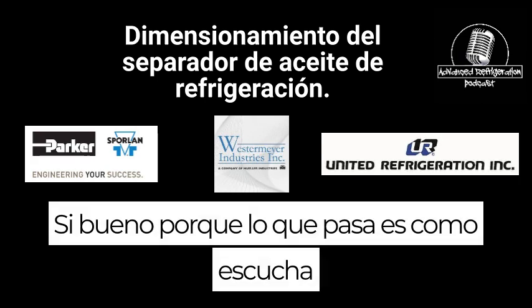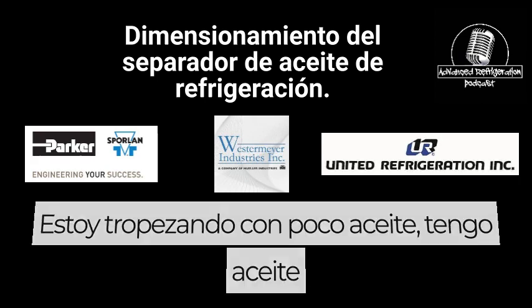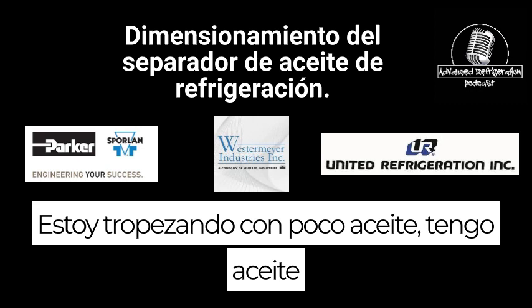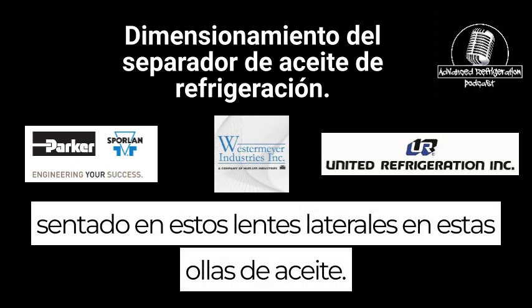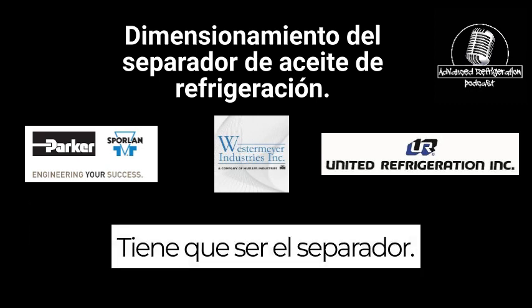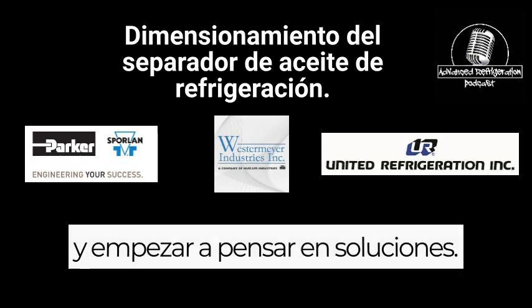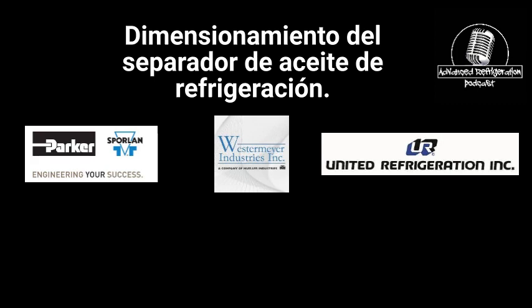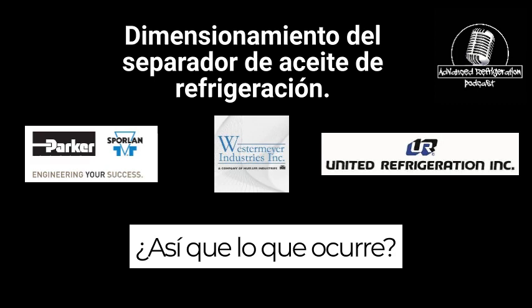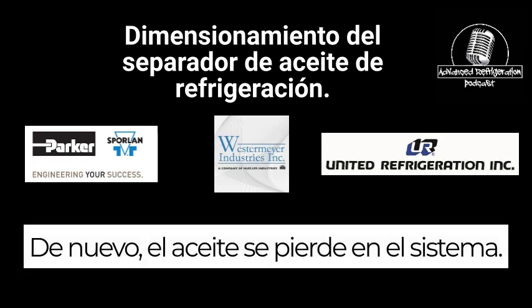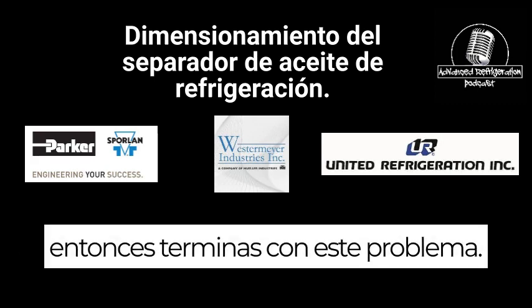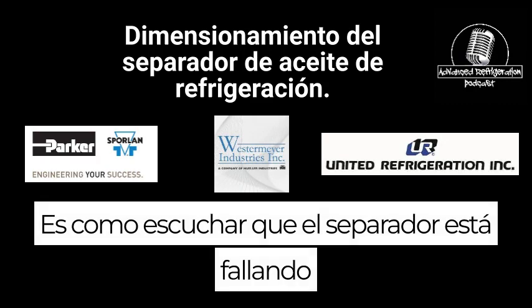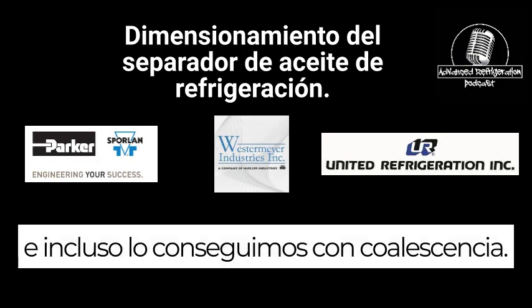Yeah. Because what happens is, listen, I'm tripping on low oil. I've got oil sitting in the side glasses on these oil pots. It's got to be the separator. You've got to fly out here and start coming up with solutions. Oil gets lost out in the system, and then you end up with this problem. It's like, that separator's failing. And we even get it with coalescing.